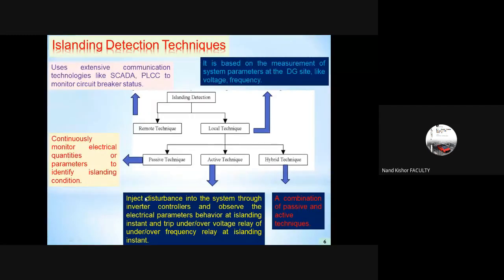In this case, we try to inject some disturbance into the system, and it could be through the inverter controllers, right? So we keep on injecting some disturbance into the inverter controllers and thereby observe the electrical signal characteristic, so as to know whether there is an islanding event occurrence or not. And thus, we have the under voltage or over voltage relay, or under or over frequency relay to give you an indication about the islanding event occurrence here.